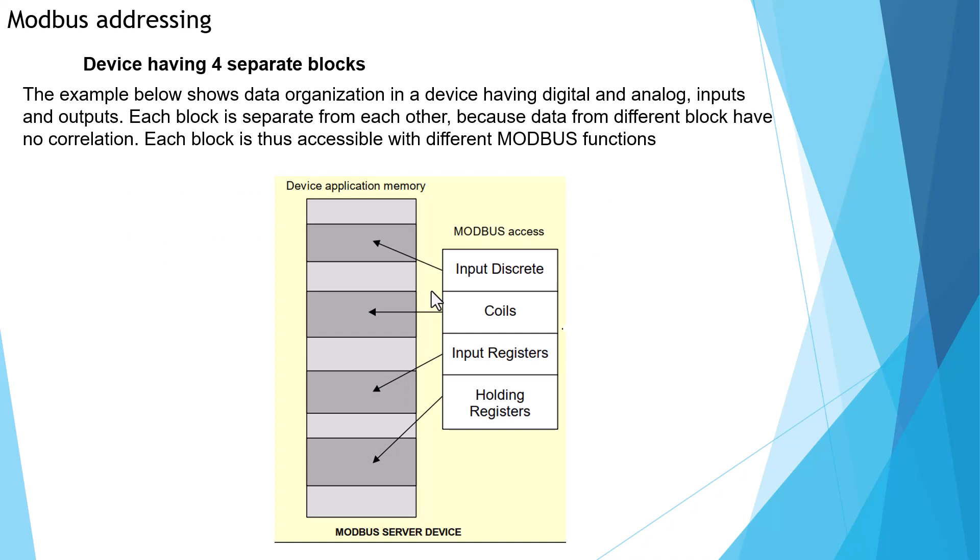There are things about Modbus address you should know. Modbus is a block. If you use Modbus, you should know it has four separate blocks: the input discrete block, the output discrete block, the input register block (analog input), and the holding register block (analog output). These four blocks are separate — they are not correlated. Each block is accessible with a different Modbus function.